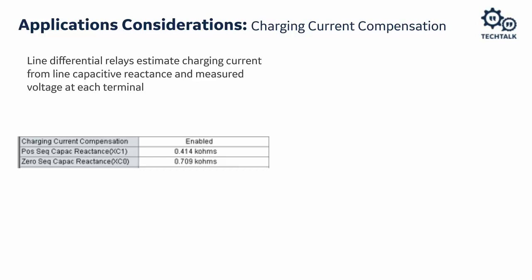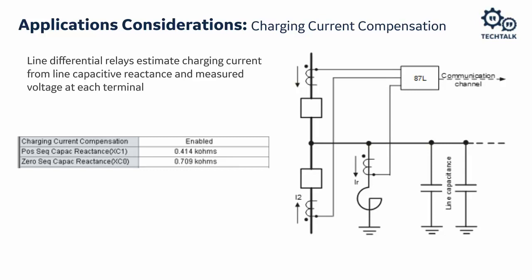A complication arises because the reactor can be switched on or off, and when it is on the effective charging current changes — requiring adjustment of the capacitive reactance setting. With reactors at both ends there are many combinations. To avoid this complexity, the recommended approach is to provide the reactor current as a third input to the 87L relay, which subtracts the reactor current directly. This makes the charging current a steady, known value without needing to monitor reactor breaker positions or switch settings.